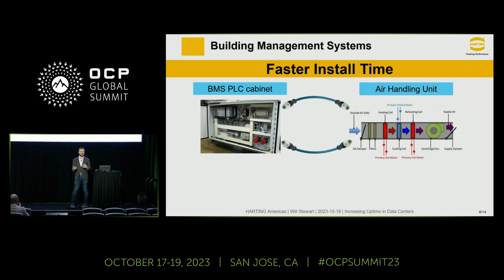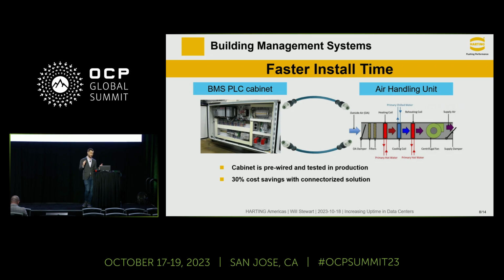What we have found is that taking away the hand wiring and replacing it with control signals like M12, M17, M23s, depending on your system, you can get cost savings - we have cases with a 30% cost savings with a connectorized solution. Obviously the M12 is going to have a little more capital expense than just flat wires, but if you look at the labor you can save, it came out to 30%.